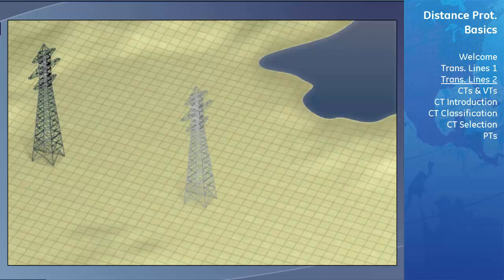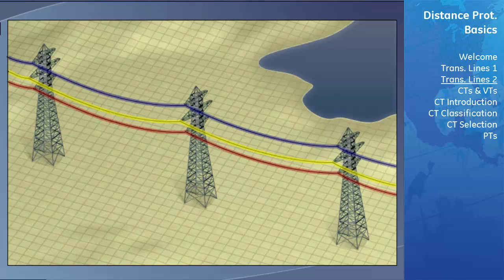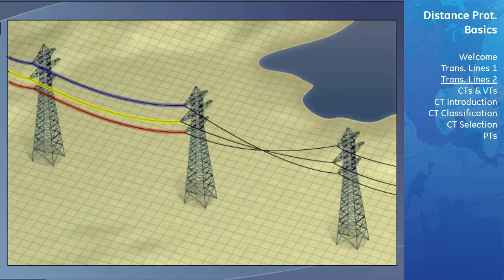Transmission lines in fault calculation studies are generally considered to have conductors where all three phases are symmetrical with respect to each other and the ground — that is, they have identical characteristics. However, in the common configuration where all three phases are hung vertically, the characteristics of the different phases are not actually symmetrical due to the difference in height of each phase. This is the reason that some line sections are transposed, where the order of the transmission lines is reversed so that these characteristic differences can balance off and the total line can be approximated as symmetrical.